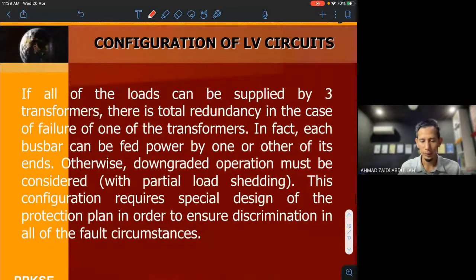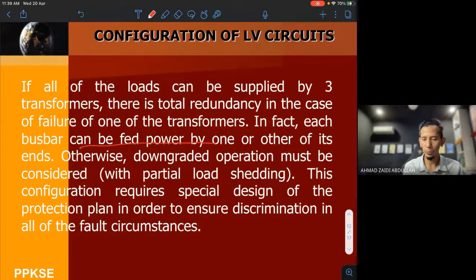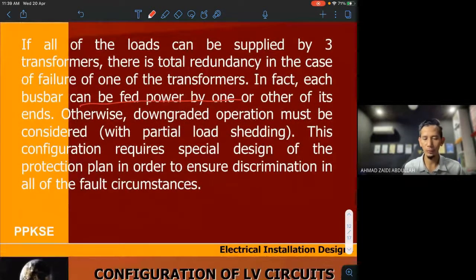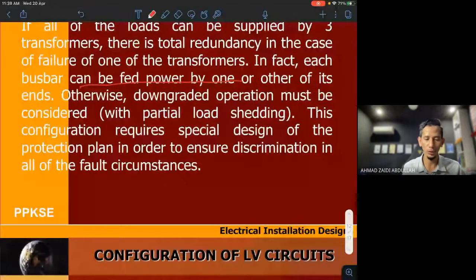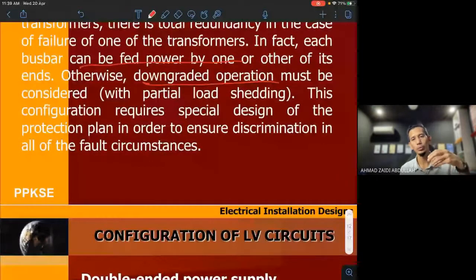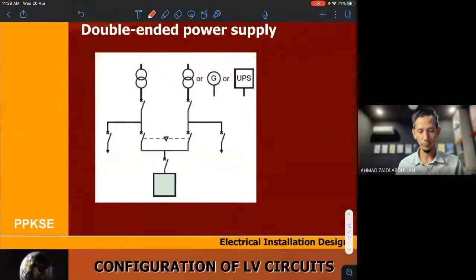Okay. In fact, each busbar can be fed power by one of the others. Otherwise, downgrade operation must be considered. So if that issue arises, you need to downgrade. Maybe instead of your load of 2000 amp, you try to downgrade to become only maybe 500 amp. So at that time, you can still operate but at very low output.